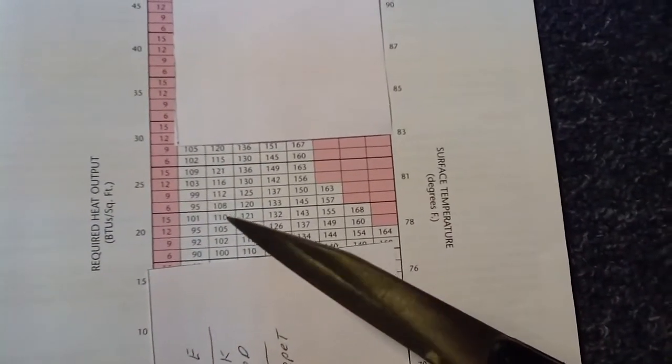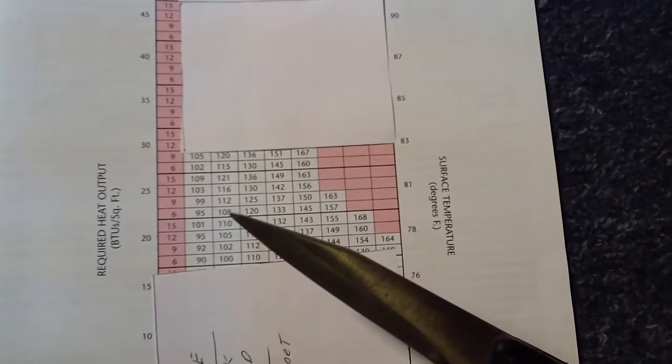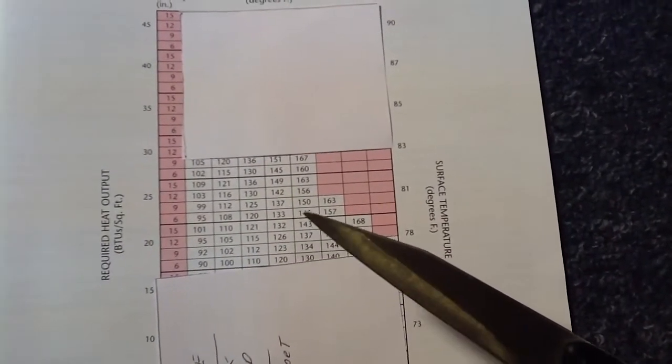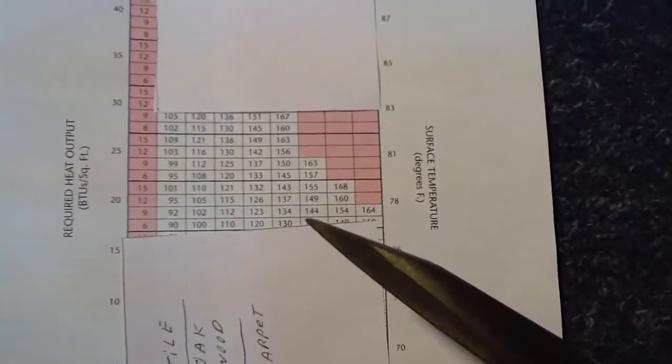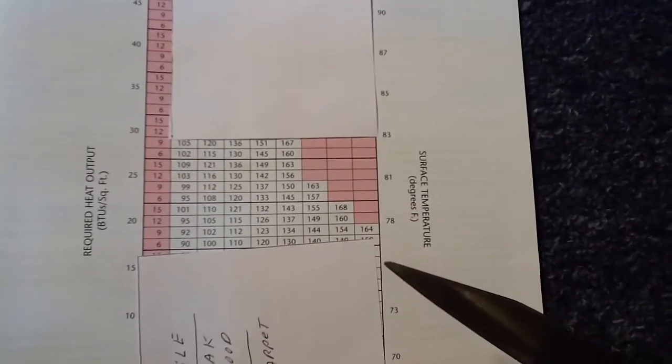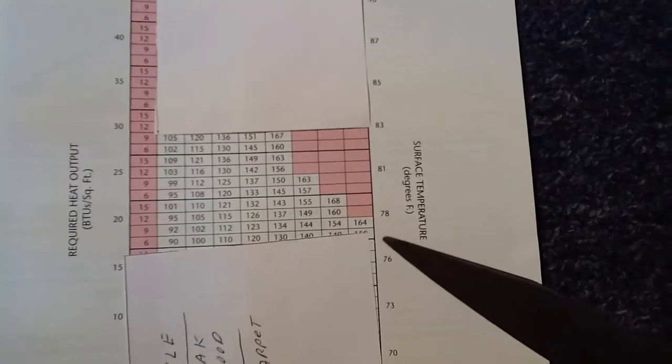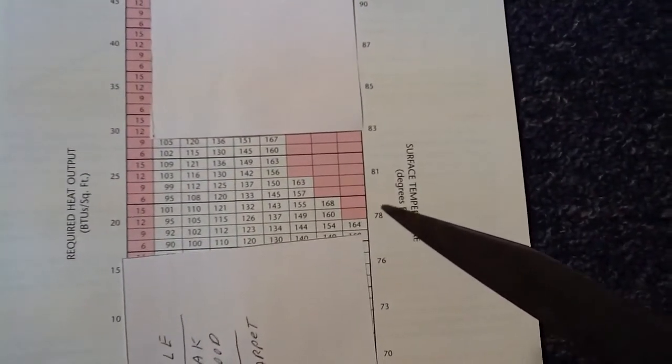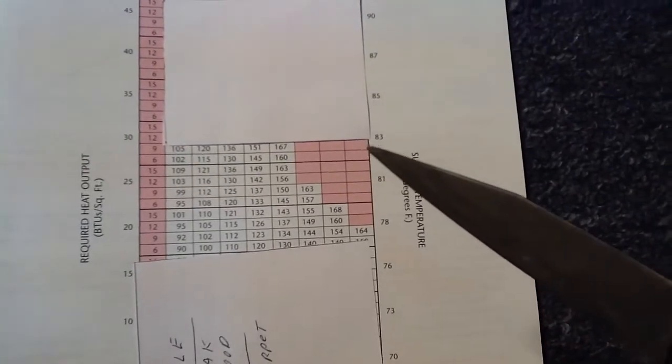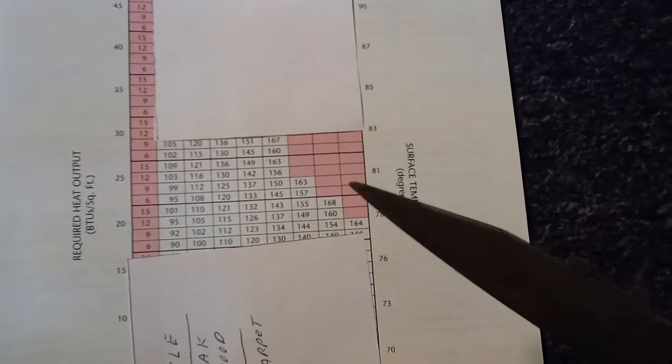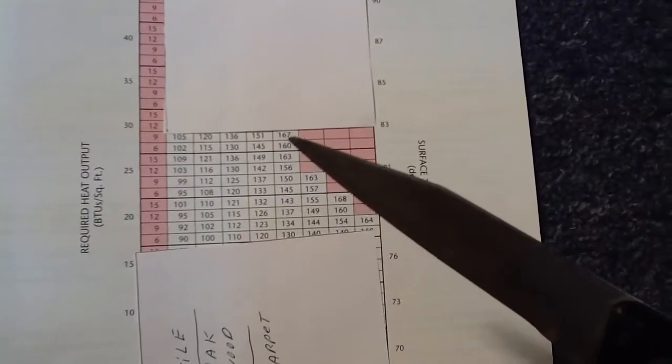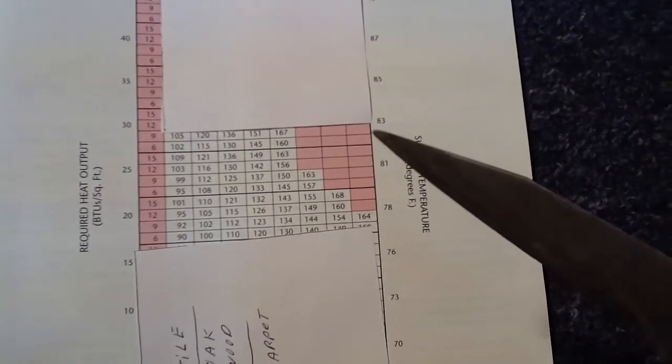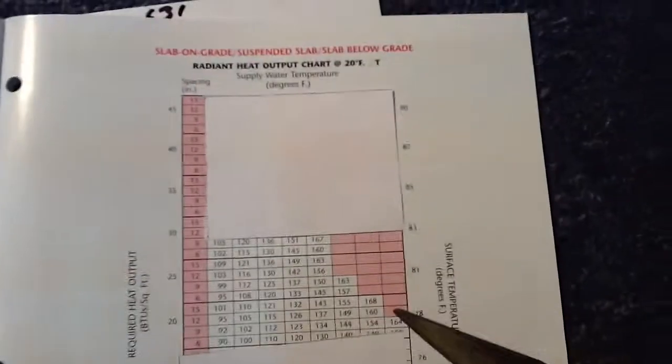And as you can see, the hardwood floors, 108. And as carpet, the water temperature gets higher, 120, 133, 145. Now, don't forget, this will give you floor surface temperatures on this side of 78 and 81 or 83, the floor surface temperature, as the floor surface temperature is going to get higher also.